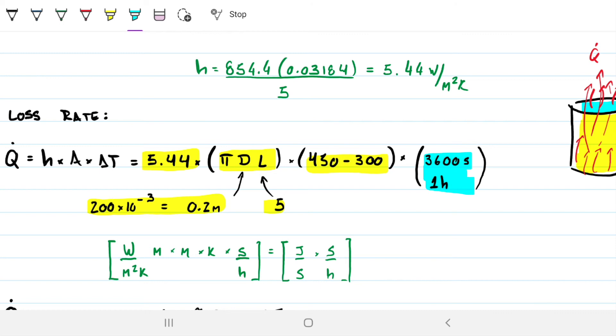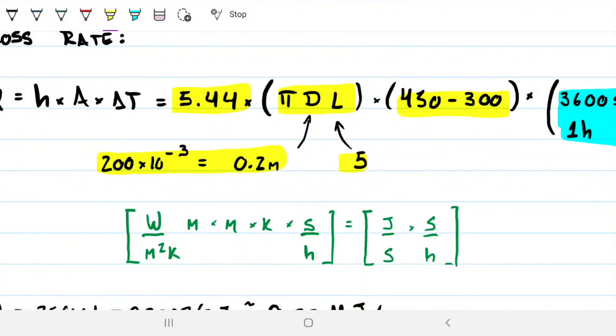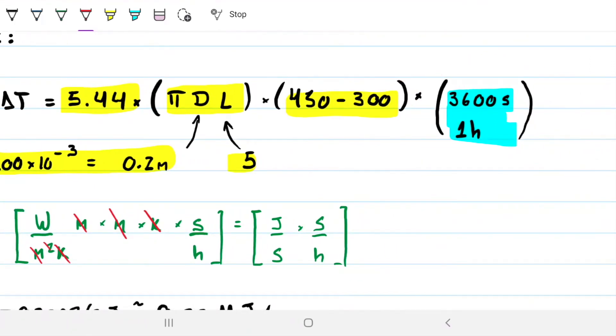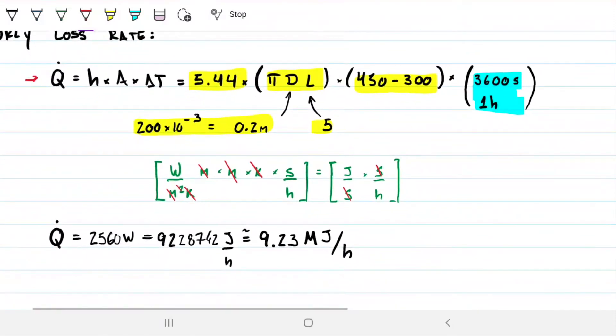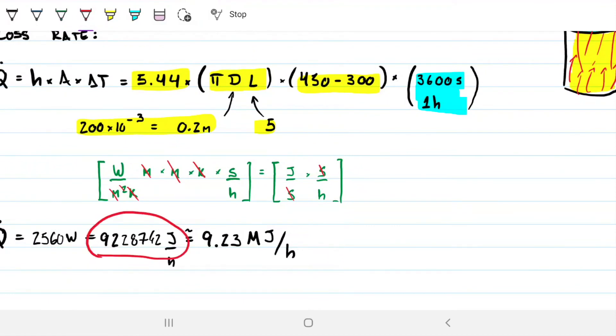Now, the hourly loss rate, which is what we're after for this guy, is going to be Newton's law of cooling. We have the convective coefficient. The area is going to be the outside area of the cylinder, and note here, I'm only considering, and we're going to talk about that in a second, I'm only considering this area here, so only this yellow area, the surface area of the side of the cylinder, and I'm ignoring, at least for now, this blue area here. So we are aware that we're going to have convection happen like so, because the cylinder is warmer than T infinity, so we know convection is going to make our Q leave and go upwards and rise. At the same time, we know here on the top, right on the blue part, this is also going to be taking place.